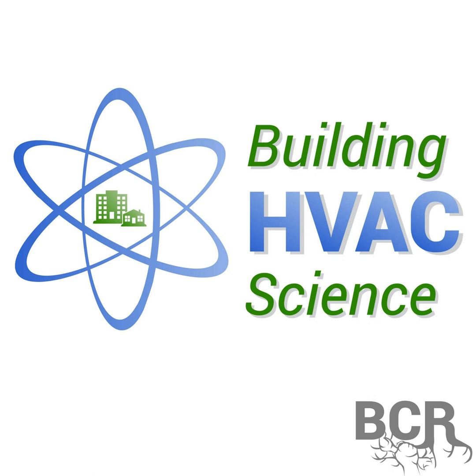In other situations, if you size the filter really, really small, or by conventional practice, a high MERV filter might eat up half or even 3/4 of your static pressure budget. And then you either sacrifice airflow or you wind up having to do really extreme large duct sizing and extremely aerodynamic duct fittings or things like that. So with a slightly larger than normal filter size, we can get that great filtration without affecting the heating and cooling performance of the system.